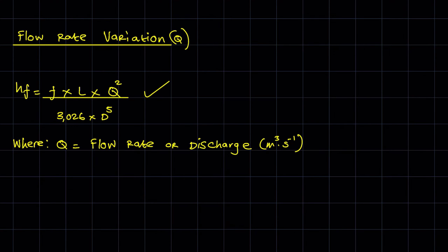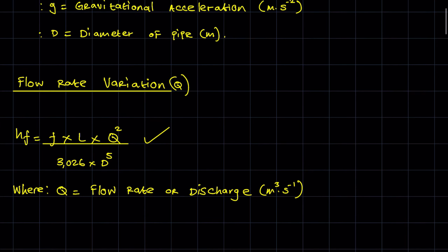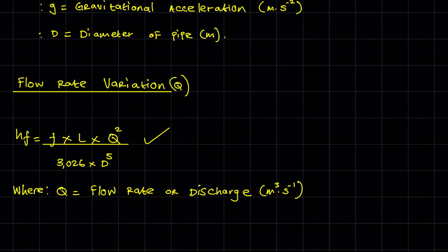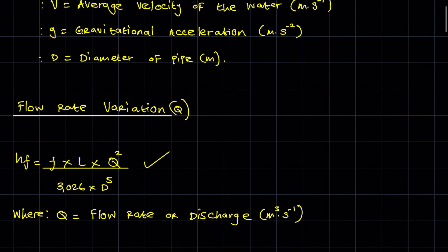Those are the two formulas under Darcy's formula. You can use either variation — it doesn't really matter. If you've been given the velocity, you can calculate Q using Q = A × v, and then substitute into the flow rate variation of Darcy's formula.